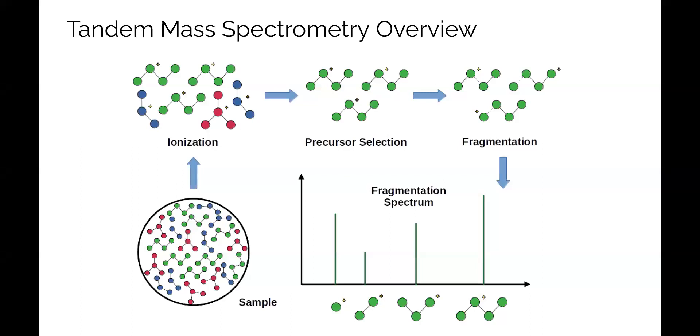Typical tandem mass spectrometry workflows consist of a few core steps illustrated here. First, compounds in the sample are ionized, allowing them to be manipulated with electromagnetic fields. The ions are moved around the instrument and sent to a mass analyzer which records their mass to charge ratio or m over z. These unfragmented ions are called precursors.